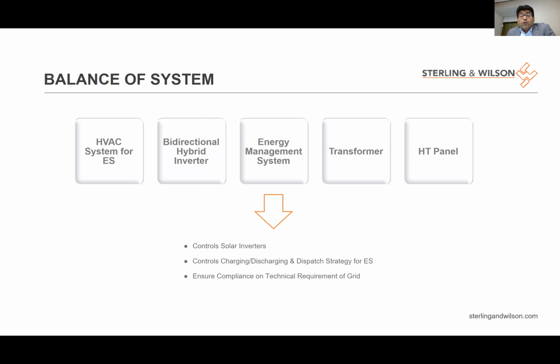You have to go for the energy management system. This piece is the most important piece in the entire solar plus energy storage plant. It can control solar inverters, control the charging and discharging of the batteries, control the dispatch strategy of the energy storage system, which is very, very important, and ensure the compliance of the entire plant to the grid requirements.